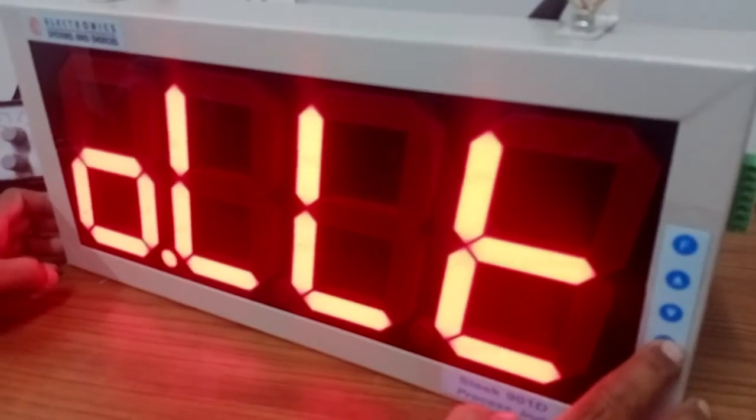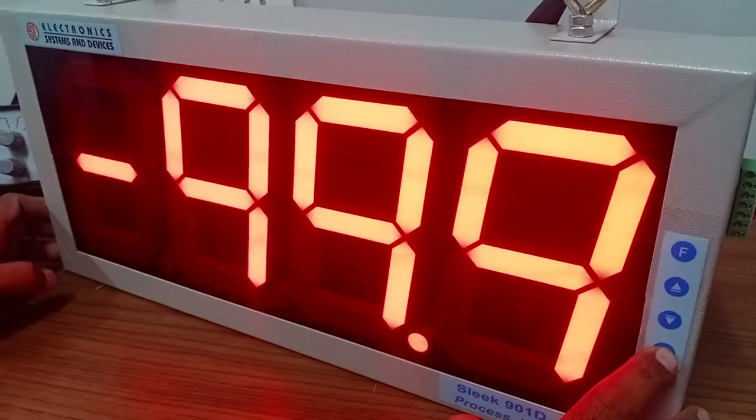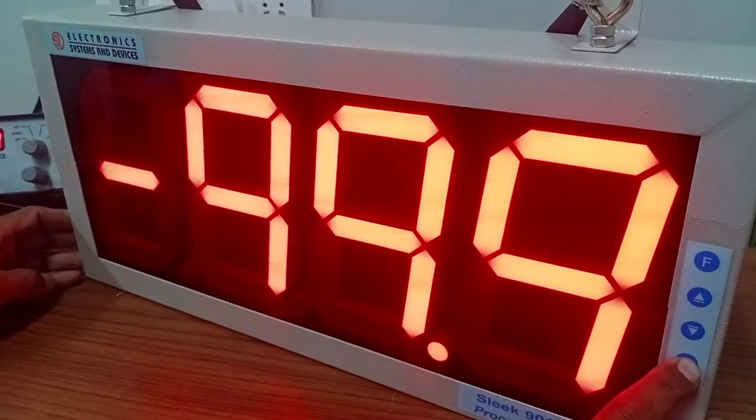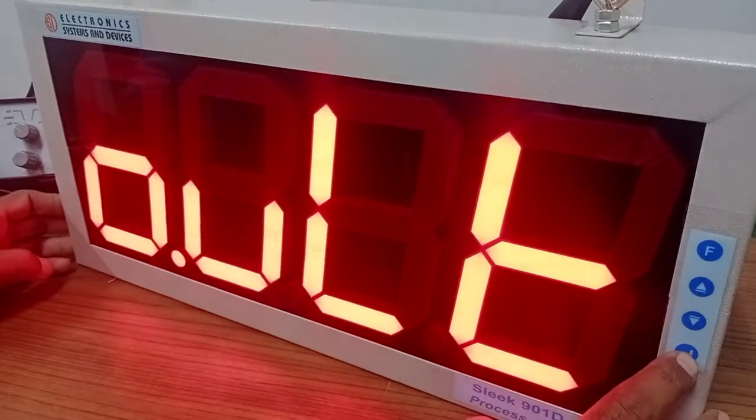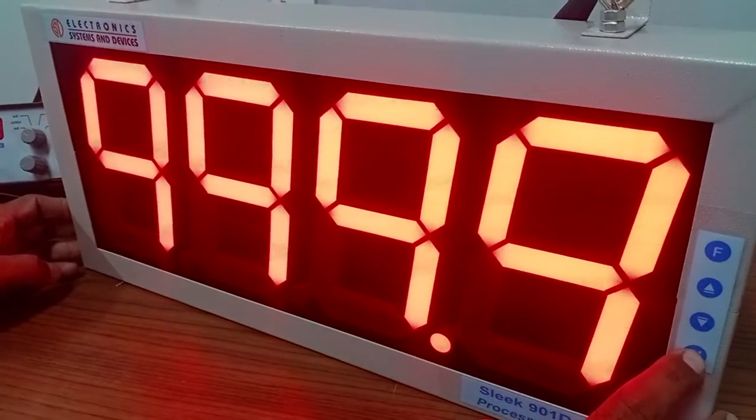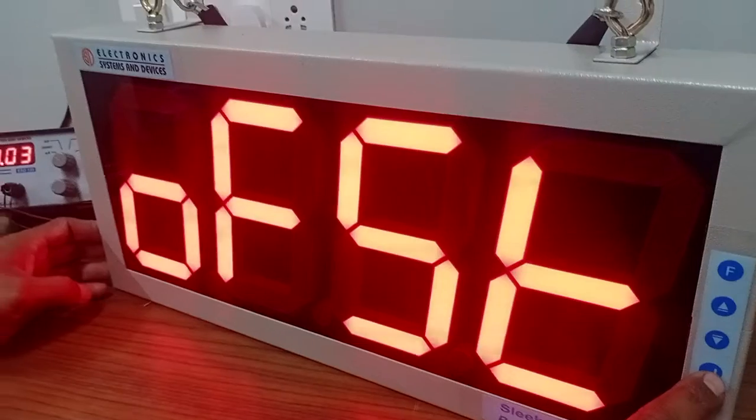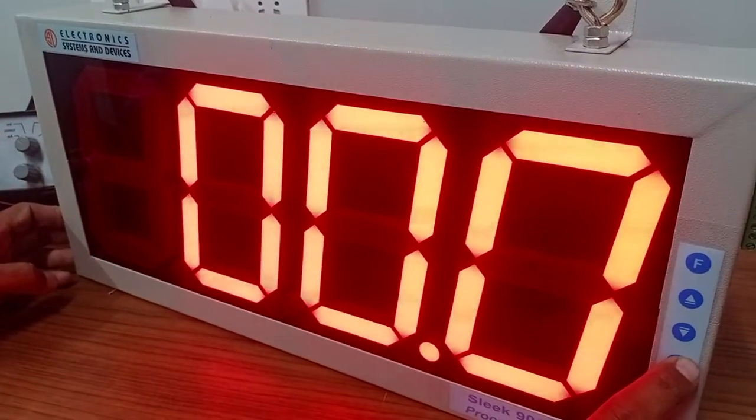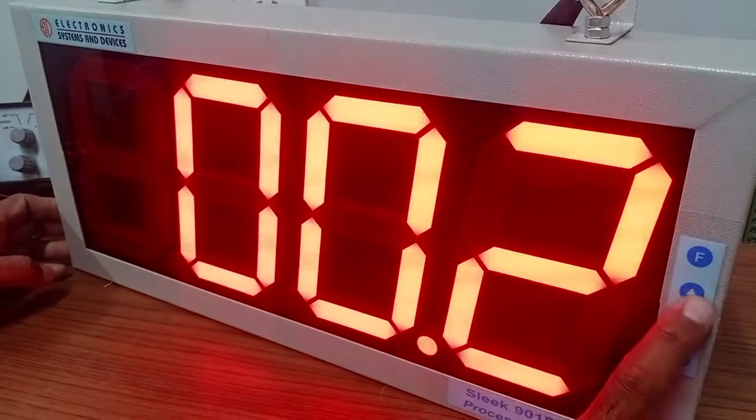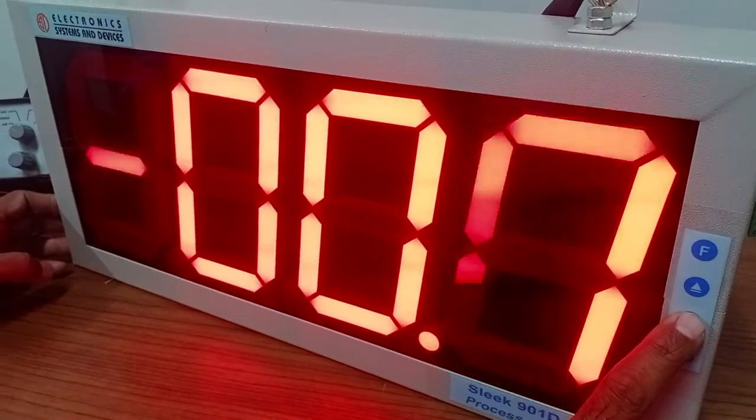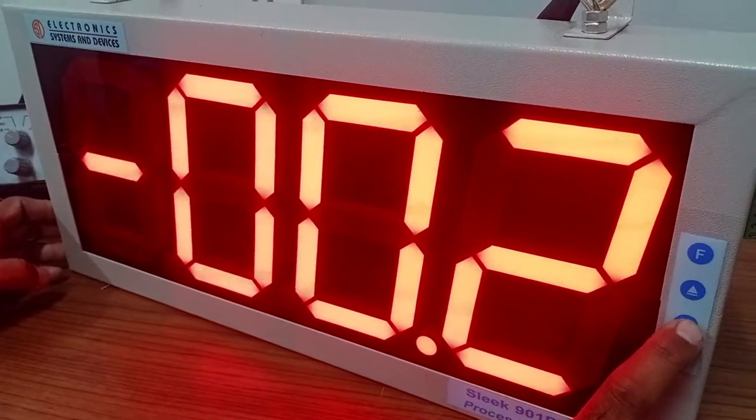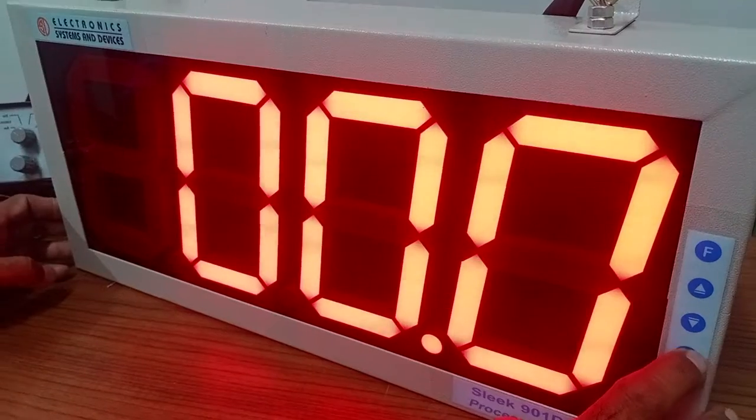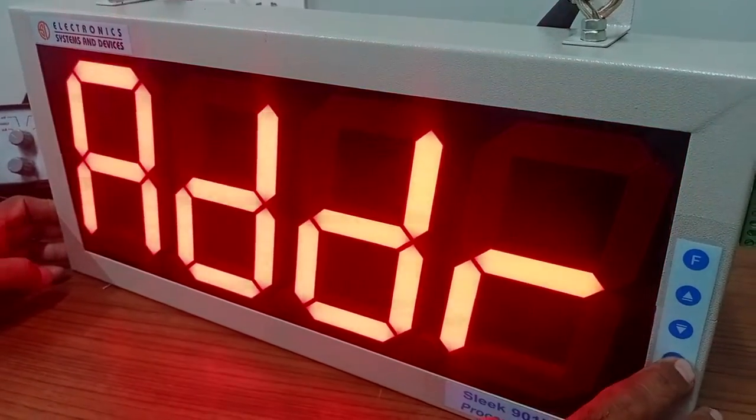This is output lower limit. This one doesn't have the retransmission output, but this is for the 4 to 20 retransmission output. Enter offset. Just in case there is some error in the sensor, you can correct that error by feeding in an offset which can be from minus 1.20 to plus 1.20. We will keep it zero.